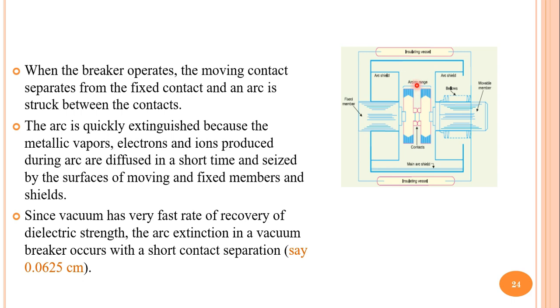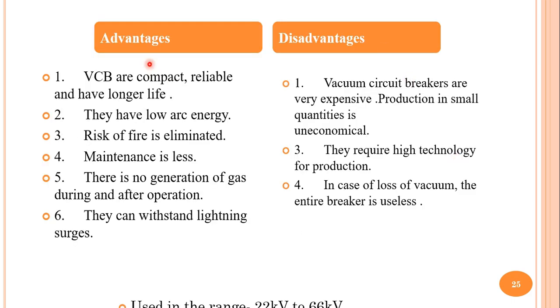Since vacuum has a very fast rate of recovery of dielectric strength, arc extinction in a vacuum breaker requires only short contact separation — the travel length of the moving contact is very small. The main advantages are that it is very compact, reliable, and has a longer life. It has low arc energy, risk of fire is eliminated, maintenance is less, there is no generation of gas during and after operation, and vacuum circuit breakers can withstand lightning surges.